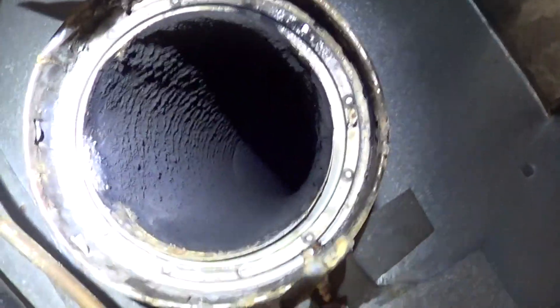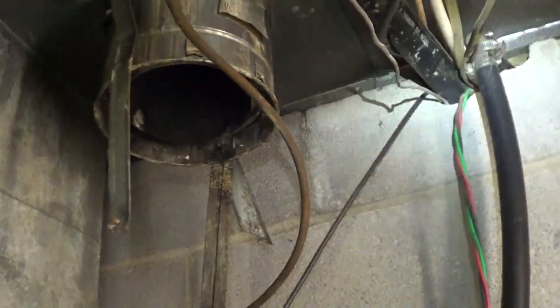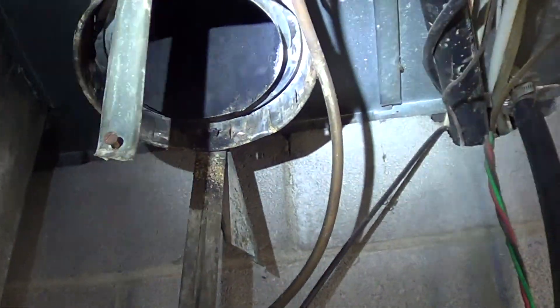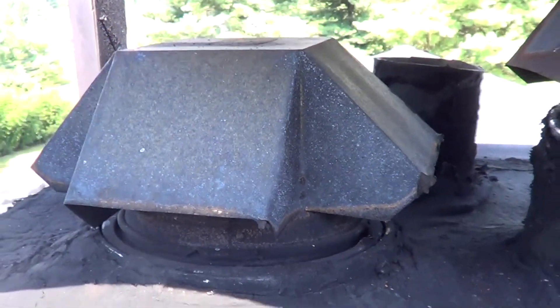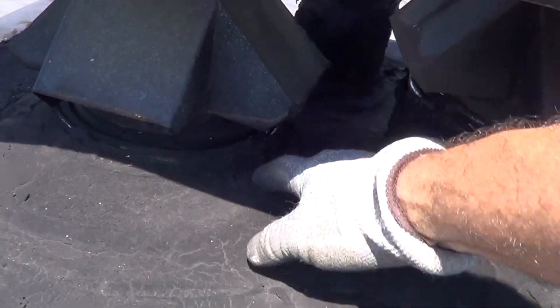So I'll be cleaning that out with a brush. I'll do that now, because I'm going to use the existing exhaust, which is a double wall aluminum lined. I'll make sure it's in good condition. Here's what we've got on top of the vent, and I'm going to change that out - it's a little bit close to the tar.